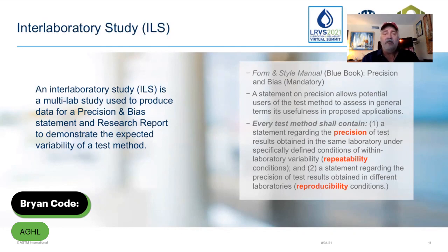And if that's done across several laboratories and the same material from each of those groupings tested by the entire population, then at the end of the day, quite a bit of data is collected. And that data is distilled through statistical methods to determine what the repeatability and the reproducibility, or another way to look at this, what the precision of the data might be.